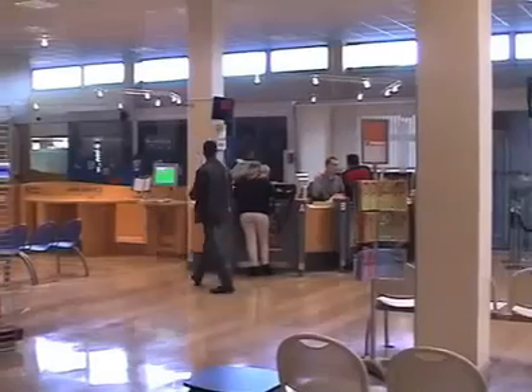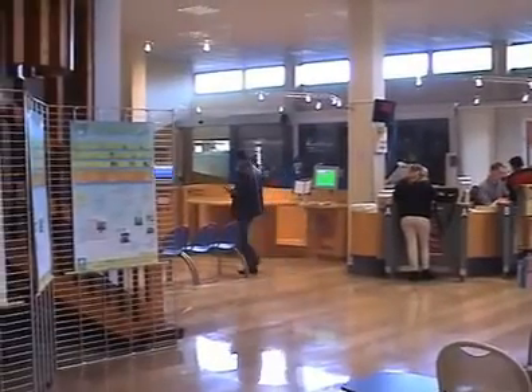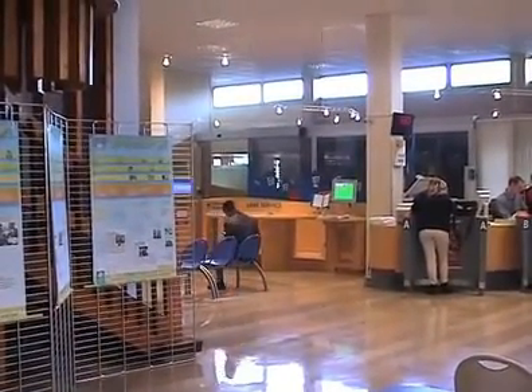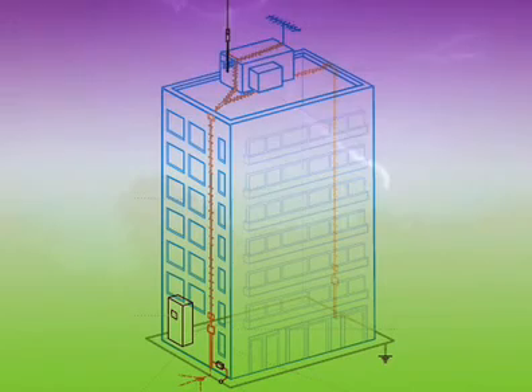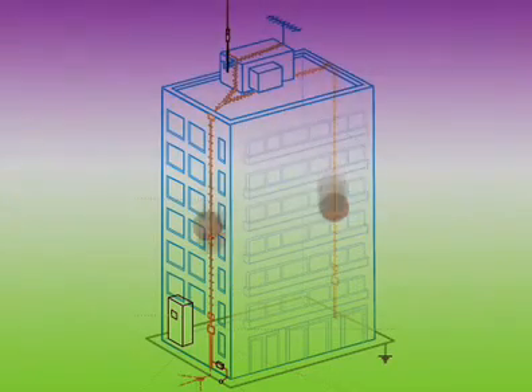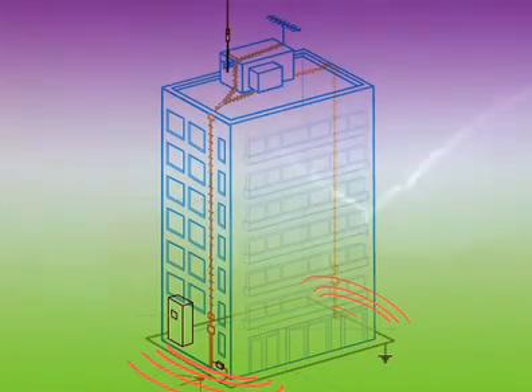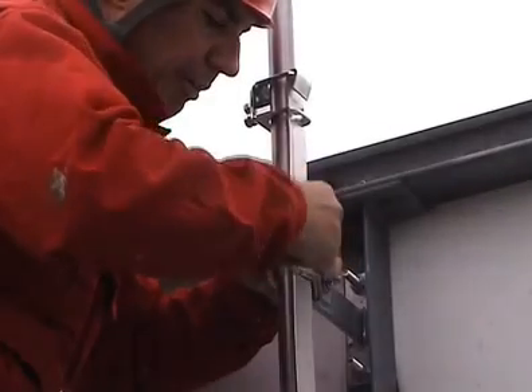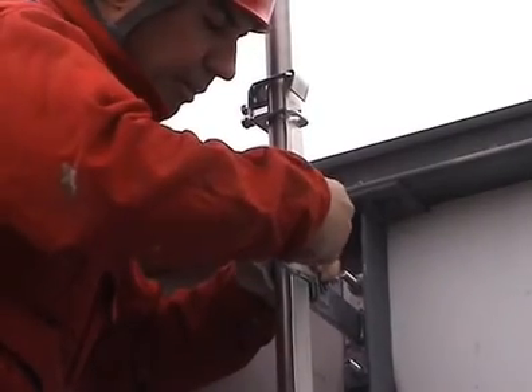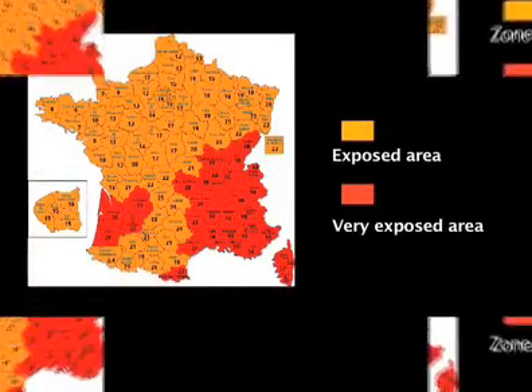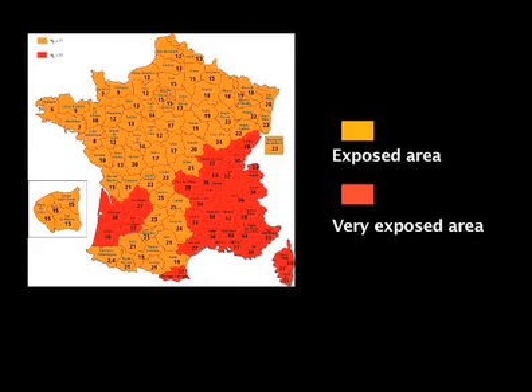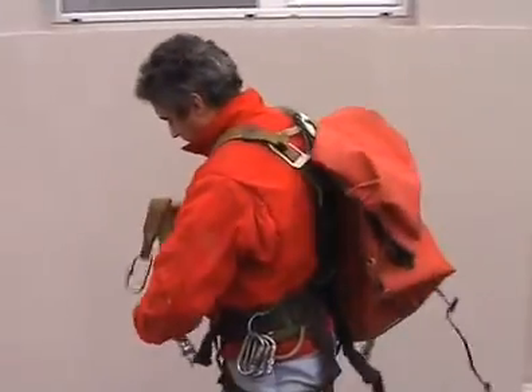When a lightning strike occurs, the lightning conductor captures the energy thanks to its active tip. The downstream conductor then leads it to the earthing system for dissipation. The installation of a lightning conductor is always done after a preliminary study of the site by a qualified professional. This person will make a recommendation based on the relevant protection needed, taking into account various elements such as the size of the structure, its location, and the lightning density of the area.